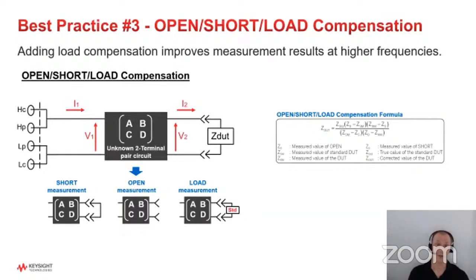So the load is actually a little trickier because you really need to have a calibrated load standard, maybe like a 50 ohm load or something. And so again, for the load compensation, you touch down with the probes to your calibrated load, and you run the load compensation. And then that actually gives you even better accuracy, especially as you go to higher frequencies, typically above about a megahertz.